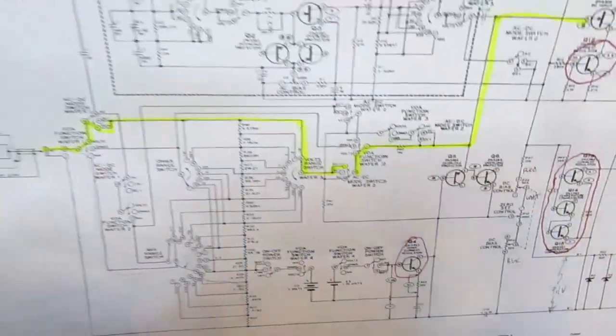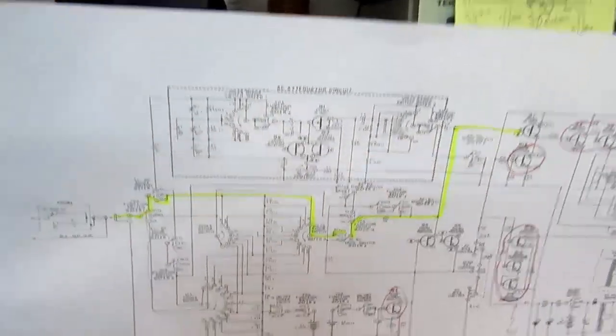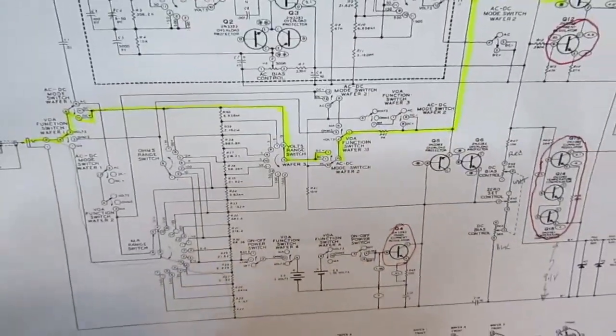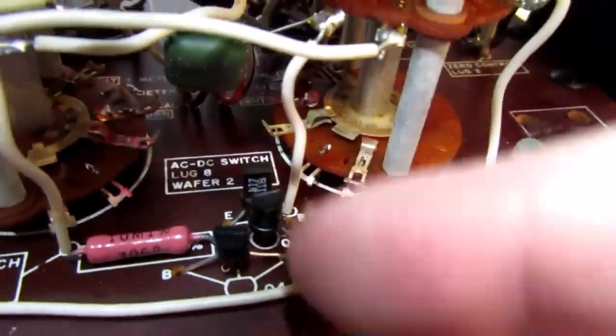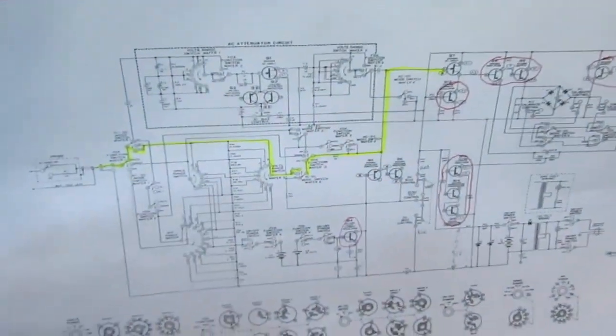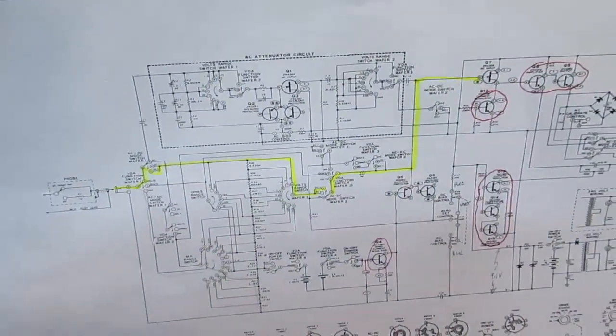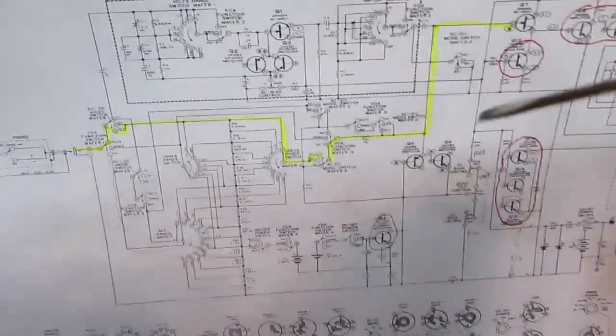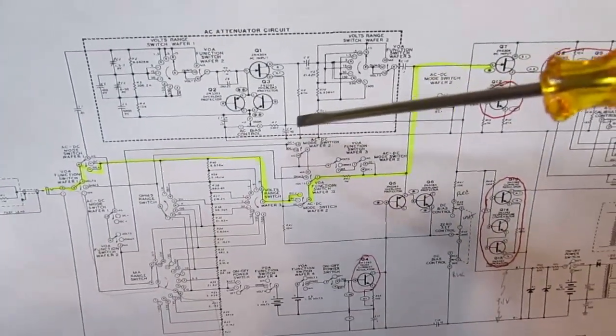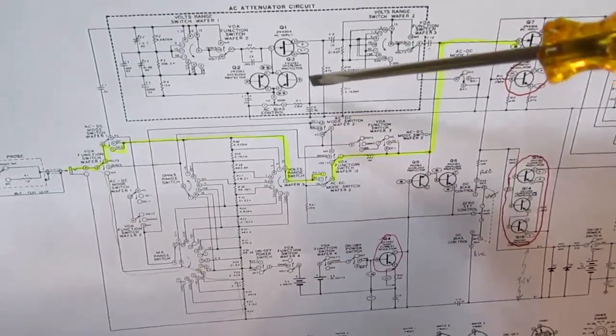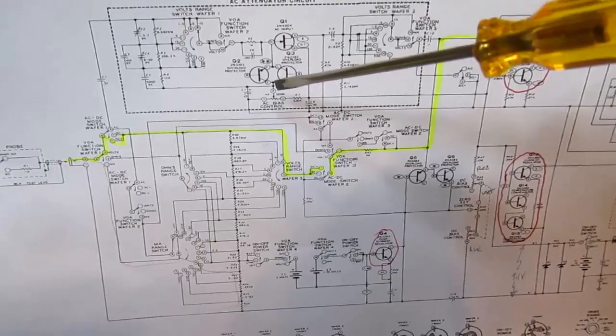I've never replaced them, and the main reason I don't replace them is, once again, they tend to be in inaccessible positions. Although some of them are better than others. Two of them are right here. There's three transistors here. It's the rear two that are sort of facing each other. The other ones are again up in a difficult to reach place right on the switches. So I don't know if those are working or not, but as long as they're not shorted out, it won't affect the meter. But if you don't replace them, you might find that the meter doesn't actually have the overvoltage protection anymore. But I think it's more likely that those are probably okay, at least okay enough that leaving them in there doesn't hurt anything.